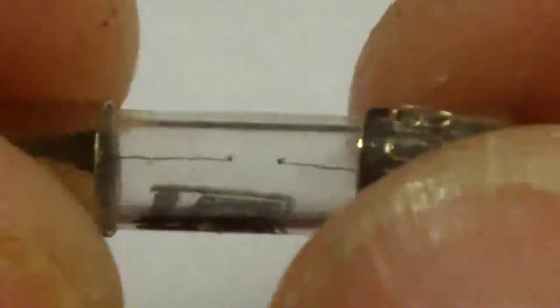By the way, it can be very useful to be able to interpret the way a fuse is blown. If you go to a piece of equipment and a fuse is blown like this, just a little melt in the middle, then what you're seeing is the wire has got hot in the middle, been cooled at the ends by the caps, and has just sort of reasonably quietly melted and blown. If there's no wire left at all, it's all vaporized and gone, then you can assume there was a fairly massive heavy short circuit. If you find a piece of equipment and the fuse has gone like that, there's a far better chance of it being recoverable than if the glass is covered in vaporized metal. That's just a little thing that has helped me to sometimes recover from a fault.